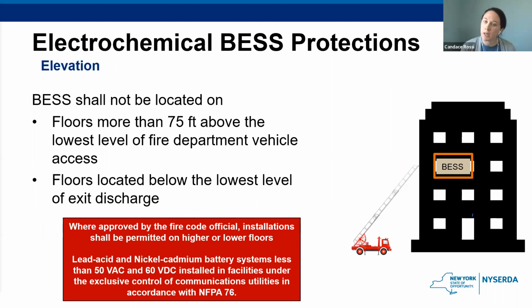Next, we have the elevation requirement. So the IFC has used this language for many sections within the fire code. The system cannot be located higher than 75 feet above the lowest level of fire department vehicle access or on floors located below the lowest level of exit discharge. So there are exceptions for each of these systems if approved by the fire code official. They can be permitted on higher or lower floors based on the additional mitigation analysis or large-scale fire testing. They can also be permitted in underground vaults if approved by the fire code official. And once again, there are specific batteries, lead acid and nickel for communication utilities, that don't have to meet this as well.